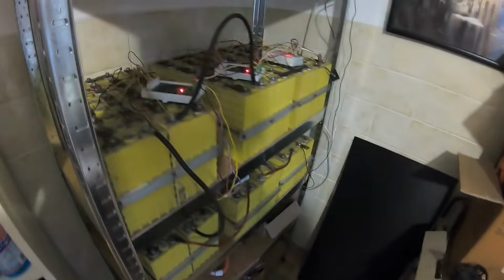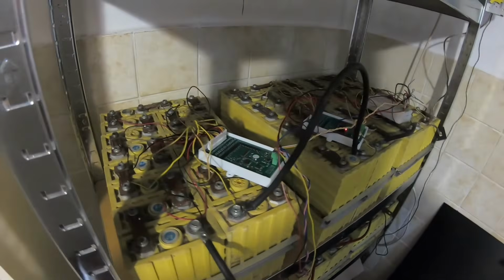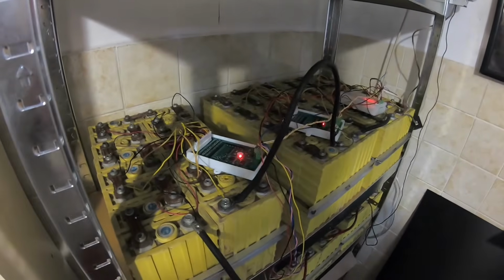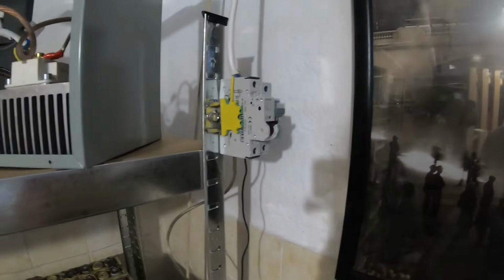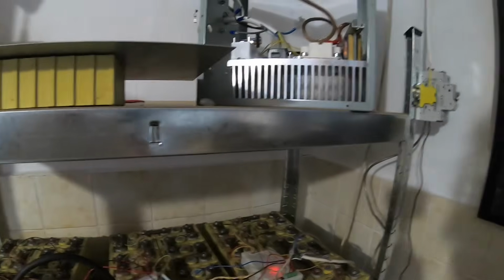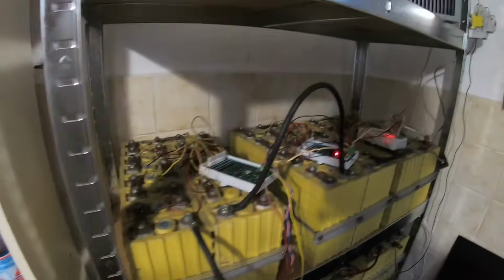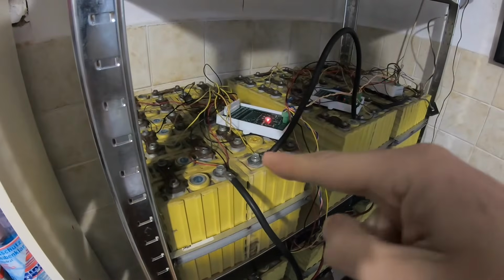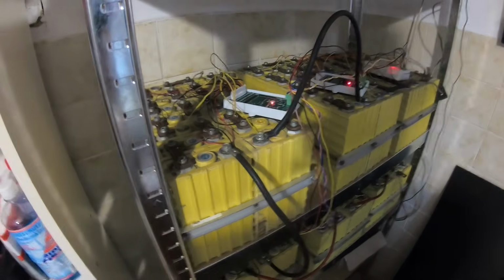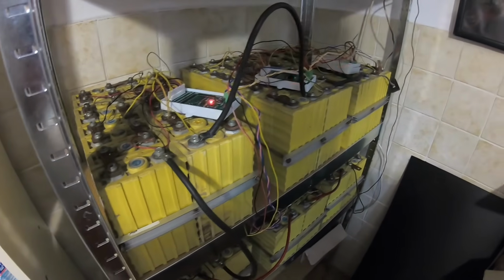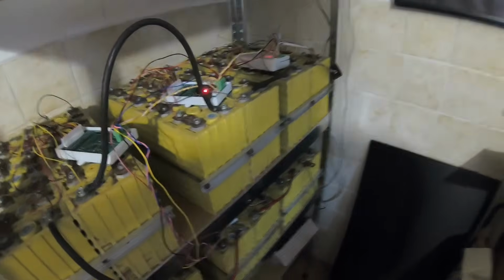This is also a nice test bench for my 16 channel BMS. We have 96 cells in series, so 6 modules in series here, all blinking away merrily. We have a circuit breaker, and the shelf is also earthed. Should something touch the shelf, since this is all grid connected, at least it's going to trip the RCD breaker.